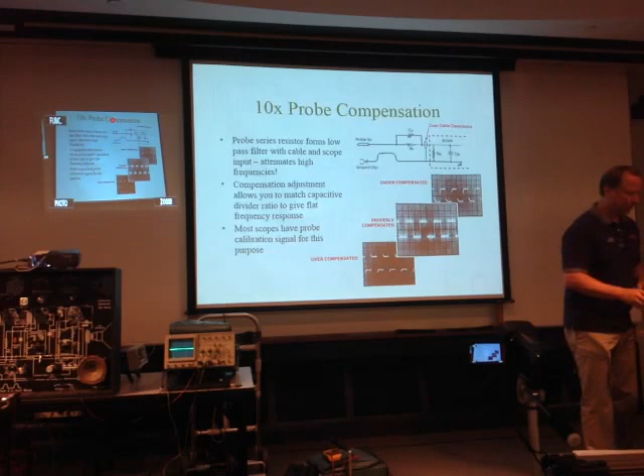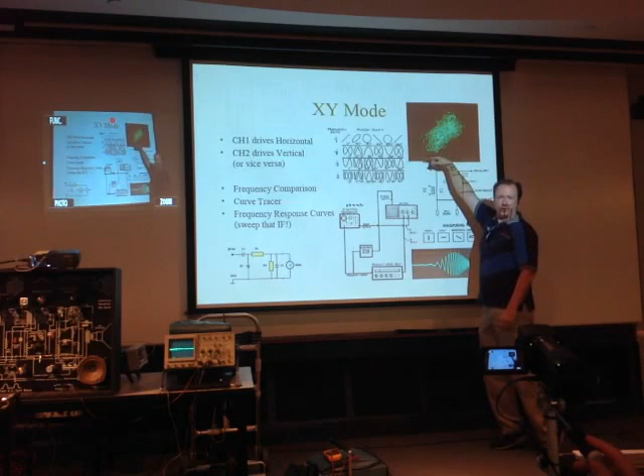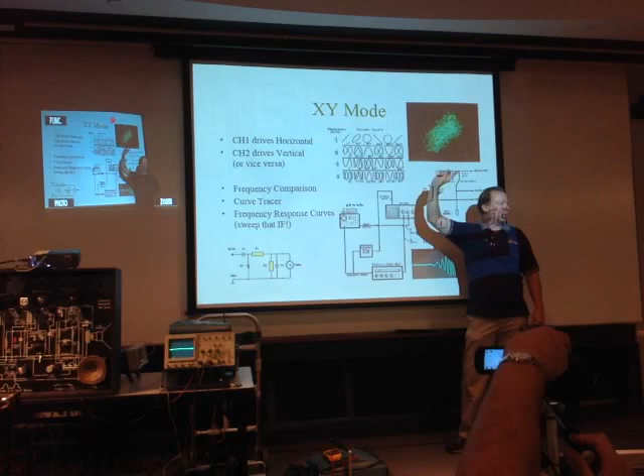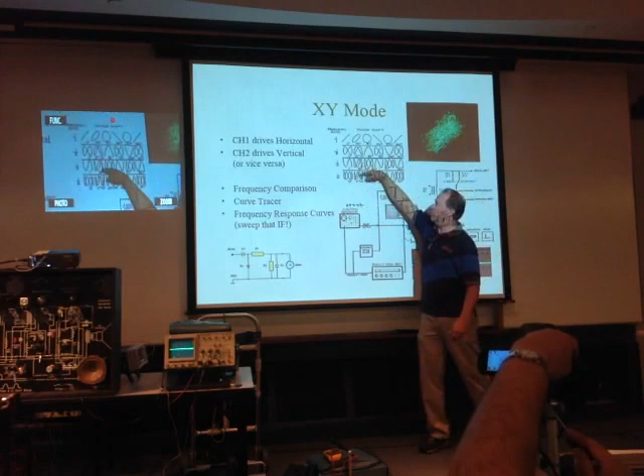The one other mode that I mentioned is this XY mode. XY mode is where, say, channel 1 drives the vertical position of the beam and channel 2 drives the horizontal position of the beam. Now, why would we want to use that? You can actually measure frequency. If you have a known frequency going into one and an unknown frequency going into the other, you can get these little Lissajous patterns, and you can count frequency ratios by the number of loops or lobes on the waveform.